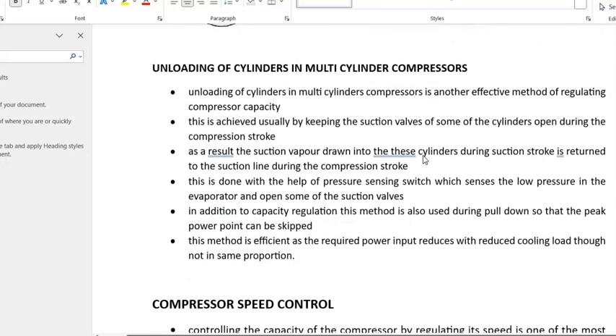Unloading of cylinders in multi-cylinder compressors. Unloading of cylinders in a multi-cylinder compressor is another effective method of regulating compressor capacity. This is usually achieved by keeping the suction valve of some of the cylinders open during the compression stroke. As a result, the suction vapor drawn into these cylinders during the suction stroke is returned to the suction line during the compression stroke.